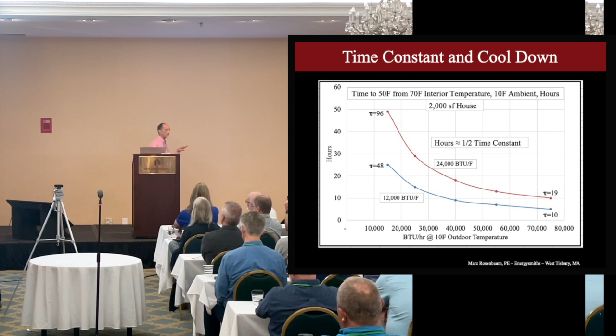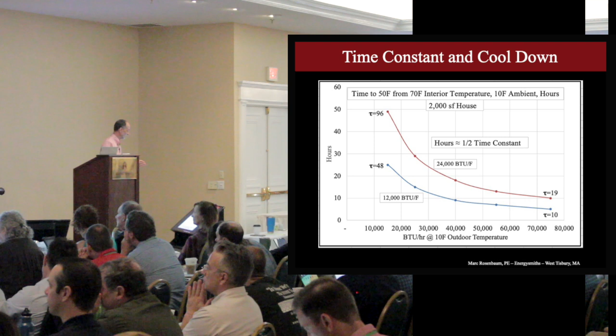I've plotted two curves here. The lower one is kind of normal thermal mass, I picked 6 BTUs per hour per degree F per square foot, and the red line is double the thermal mass. The horizontal axis is heat loss. So for the normal house, the blue line, at 75,000 BTUs an hour heat loss, the time constant is 10, and it takes 5 hours to go from 70 to 50 when the heating system's turned off.